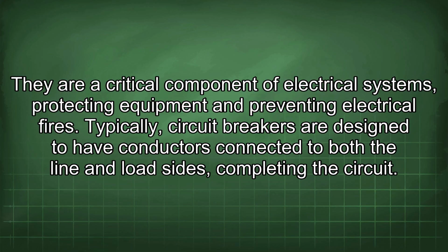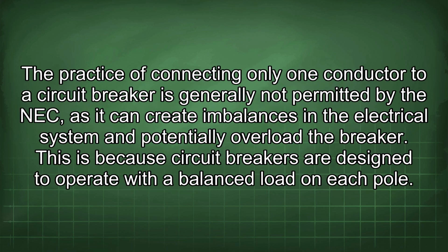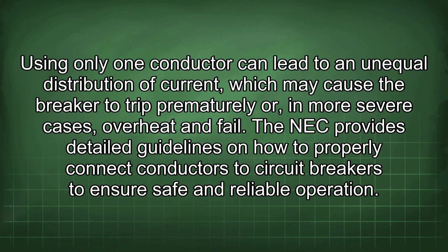Typically, circuit breakers are designed to have conductors connected to both the line and load sides, completing the circuit. The practice of connecting only one conductor to a circuit breaker is generally not permitted by the NEC, as it can create imbalances in the electrical system and potentially overload the breaker. This is because circuit breakers are designed to operate with a balanced load on each pole. Using only one conductor can lead to an unequal distribution of current, which may cause the breaker to trip prematurely or, in more severe cases, overheat and fail.